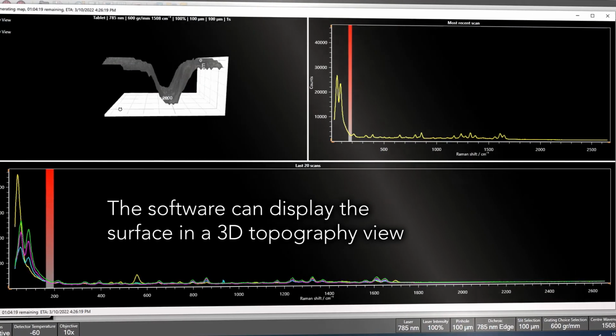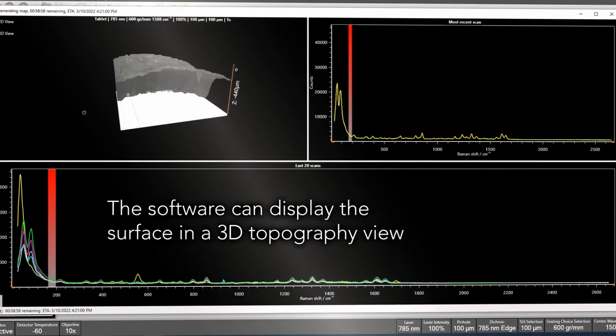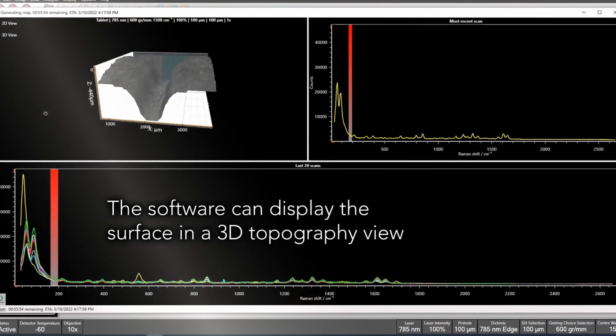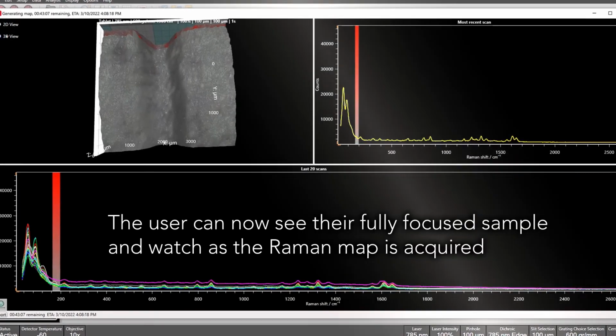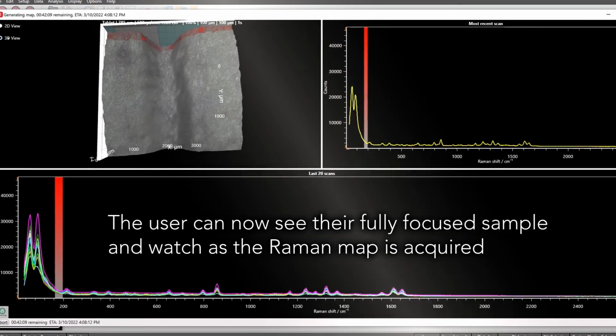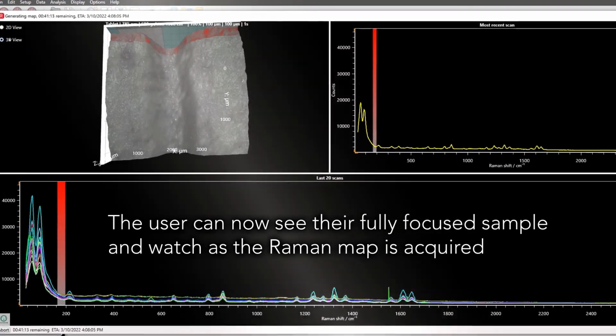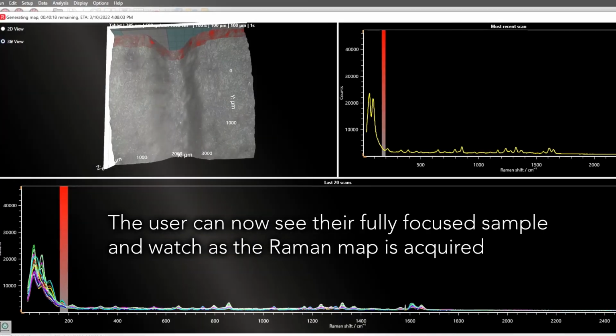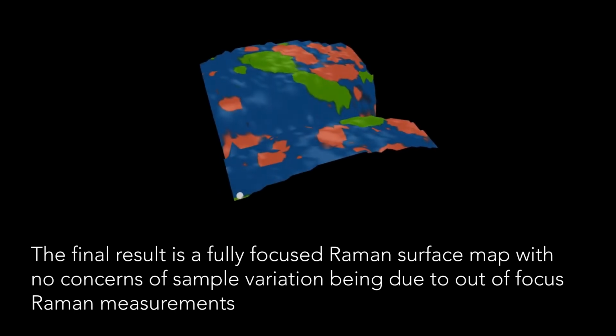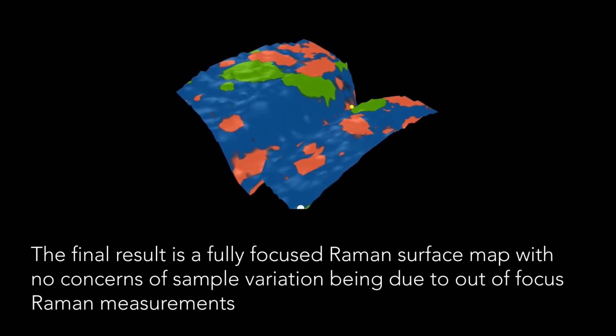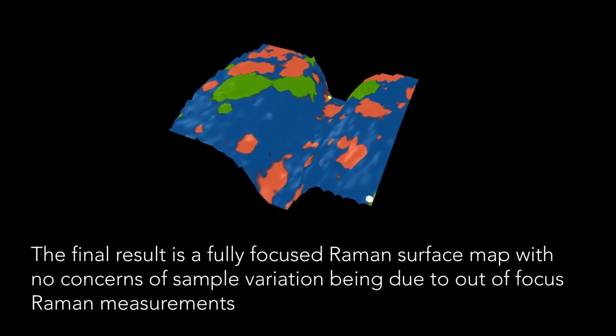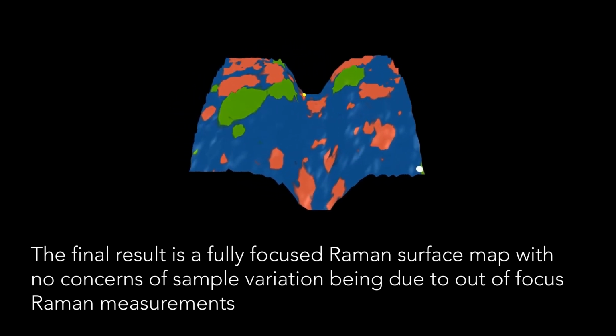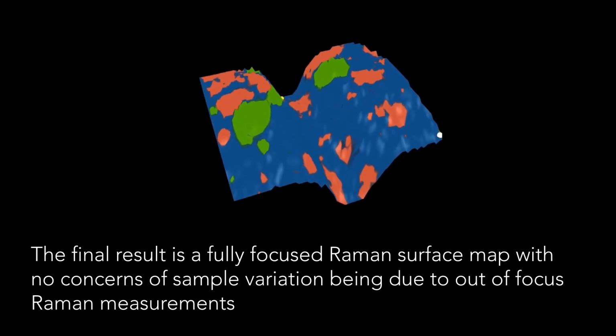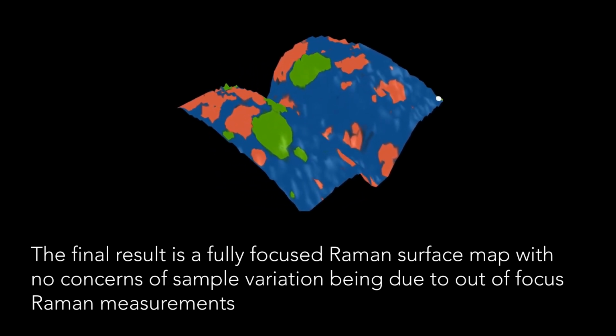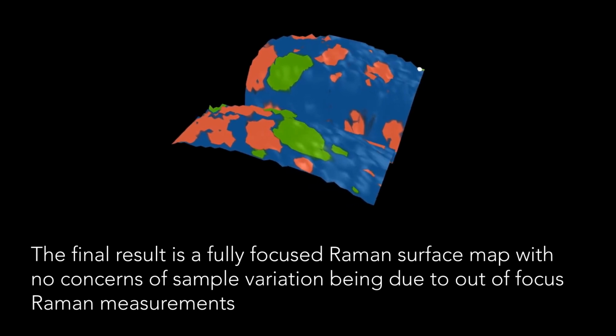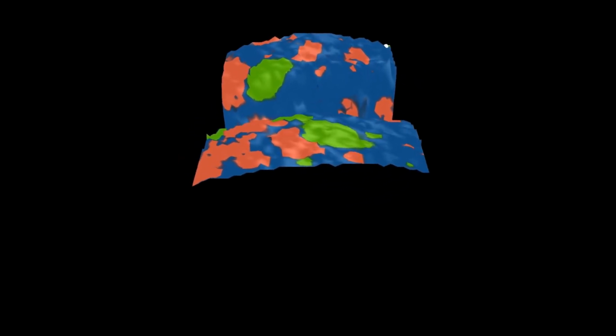Whilst the map is being acquired, the surface image can be displayed in 2D or 3D, and the user can watch as their map is running. They can clearly observe that the sample is perfectly in focus, and all their Raman spectra will be taken at the correct Z point. We now have the final result, a fully focused Raman surface map, where the user can be confident that any spectral differences are due to true sample variation and not out of focus Raman measurements.